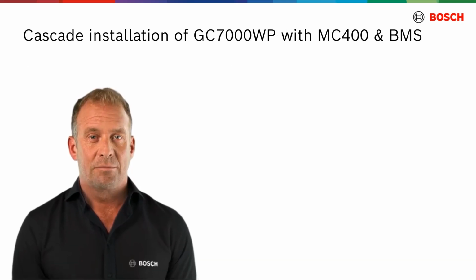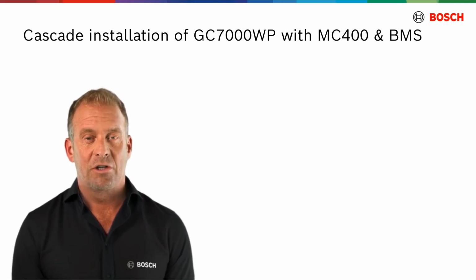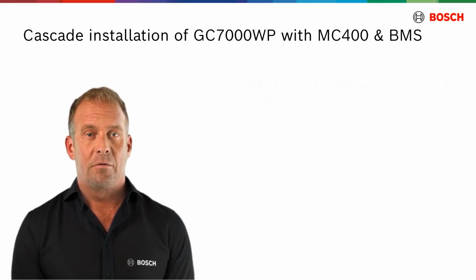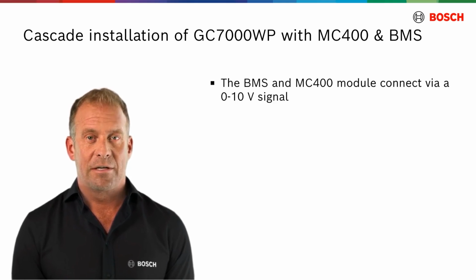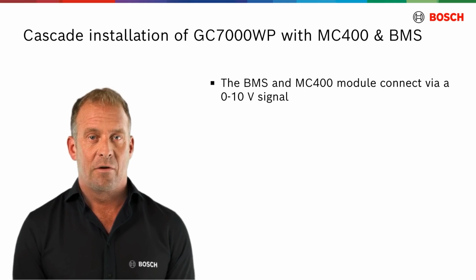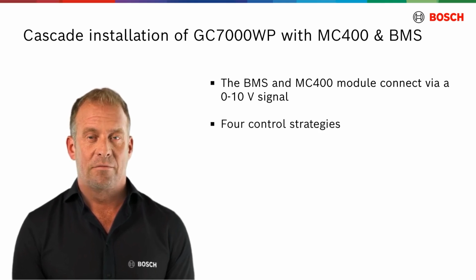In this video, we explored the integration of a cascade of Bosch GC 7000 WP condensing boilers with an existing building management system by utilizing the MC400 module. The communication between the BMS and the MC400 module operates through a 0 to 10 volt interface. There are 4 control strategies available for this setup.